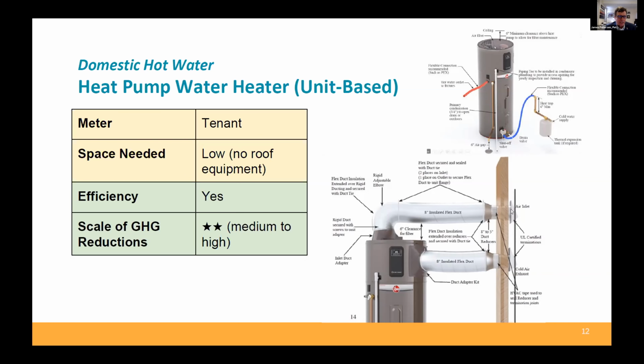So, heat pump water heaters. These have been in the marketplace for quite a while. We've been working really hard to apply them. They do not work well on an individual apartment basis, because you can imagine what we're doing is using apartment air and extracting the heat from it. So it's not hard to imagine that in order to extract enough heat to make hot water for your kitchen and showers, it's a lot. In a very small apartment, what makes this a no-go is the cold draft the equipment will produce, which will be very hard to overcome probably three out of four seasons. So we are not recommending this for individual apartment applications.